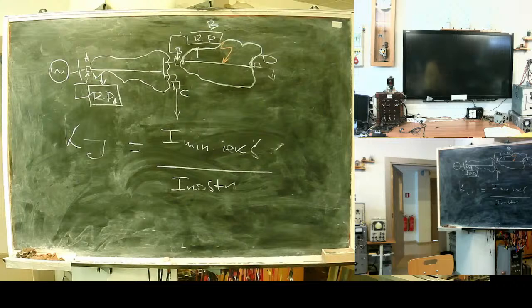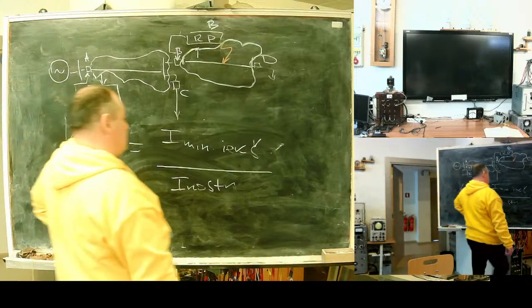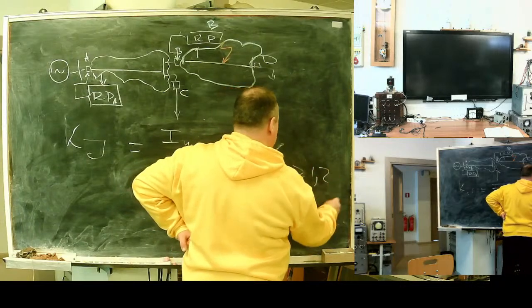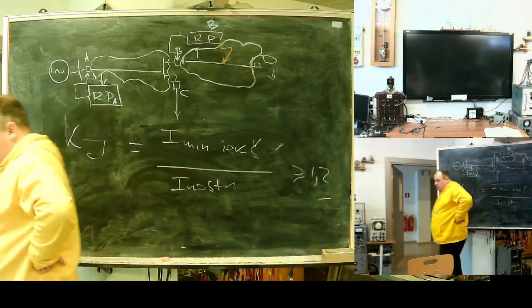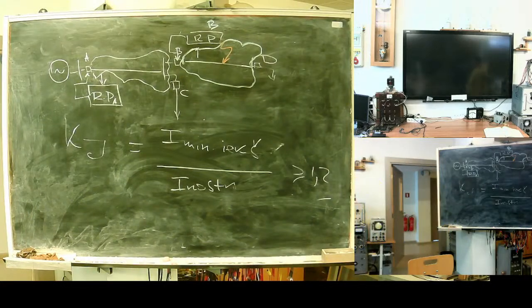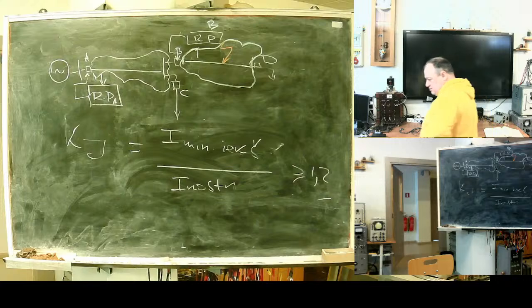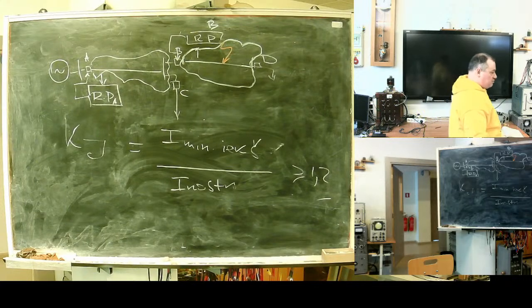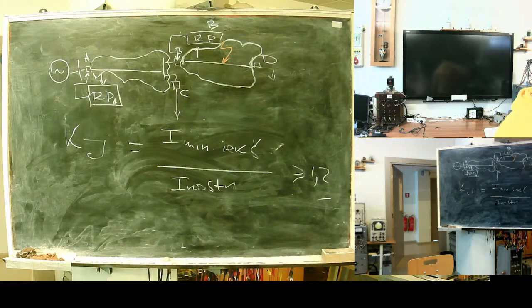So, the sensitivity factor, or jutīguma koeficients in Latvian, is the ratio between the minimal internal fault current and the set point of my protection, when to trip. Good practice is that it should be greater than or equal to 1.2. So, sensitivity, in Latvian jutīgums, is the ability to recognize internal faults. In English, the ability to sense or identify internal faults.